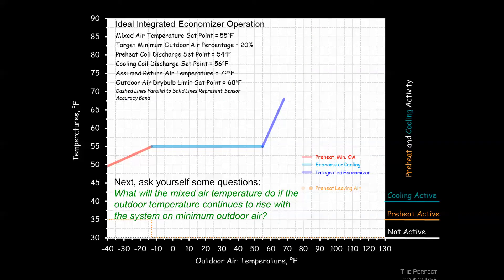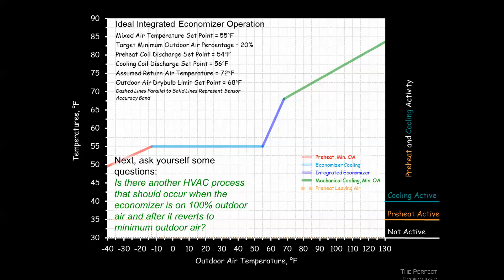Above the lockout temperature, using the same equation and recognizing the same slope as the cold-side minimum ventilation condition, we round out our economizer ideal profile. We can also mark the point where the cooling coil gets enabled at 55 degrees — when we're no longer able to use outside air alone to meet the set point.